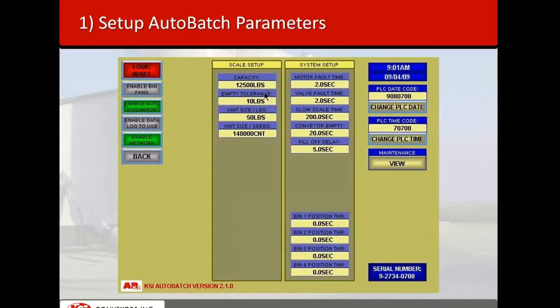The empty tolerance is how many pounds the system is looking for before it recognizes the scale as empty. In this case, when the scale reads 10 pounds or below, the system is going to say the scale is empty. The unit size is 50 pounds, so if we are running an order by units defined as pounds, it uses this field. If you're asking for 50 units times 50 pounds, as we show here, that's going to be 2,500 pounds.